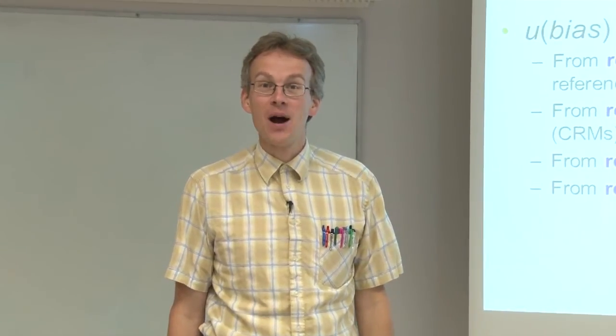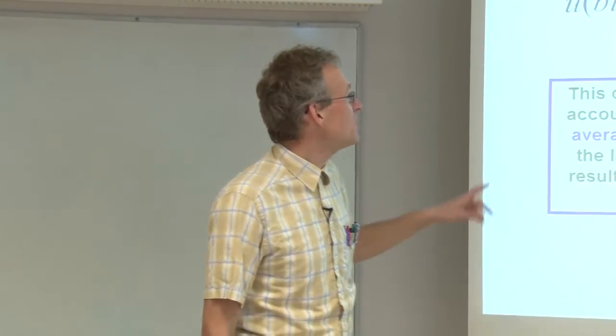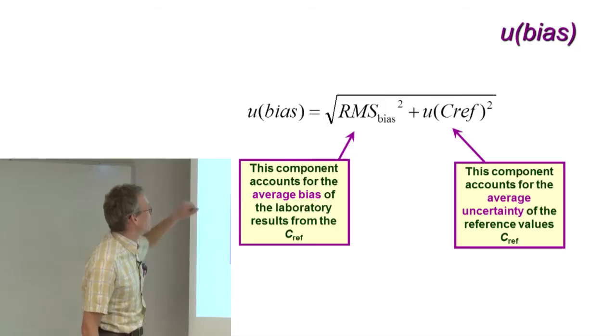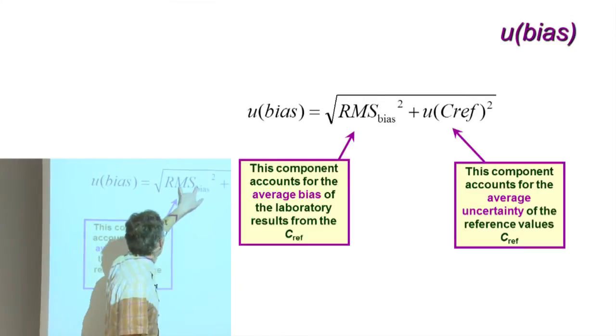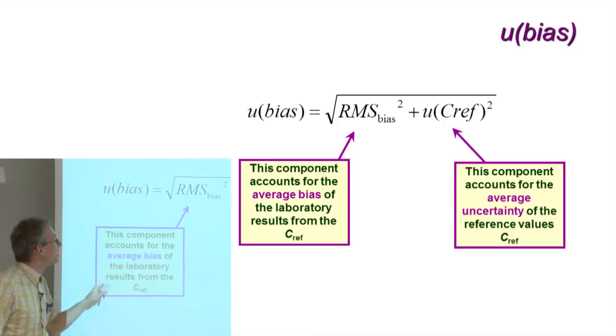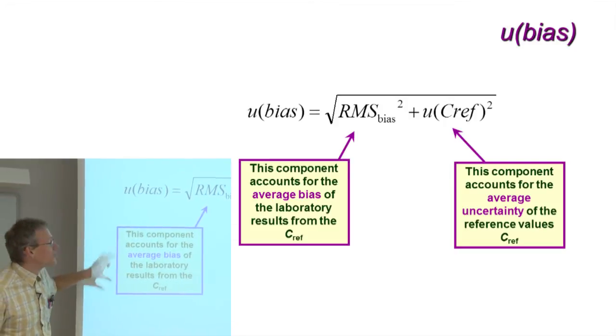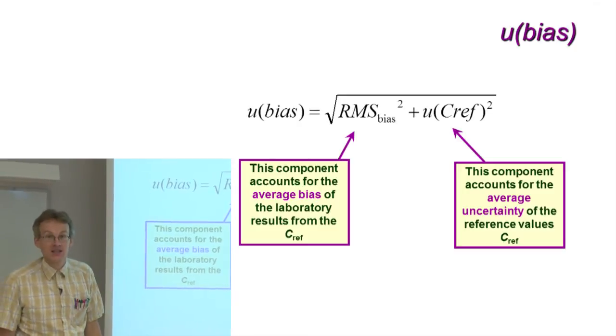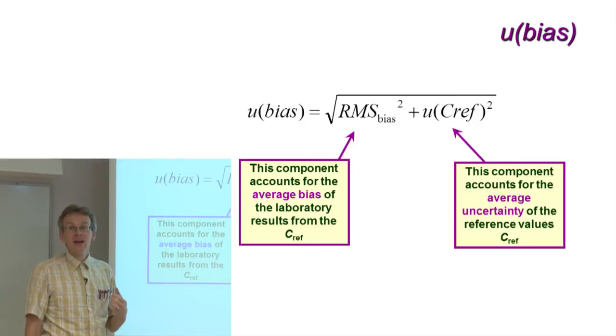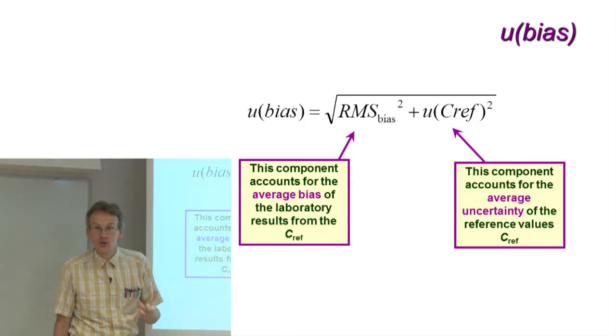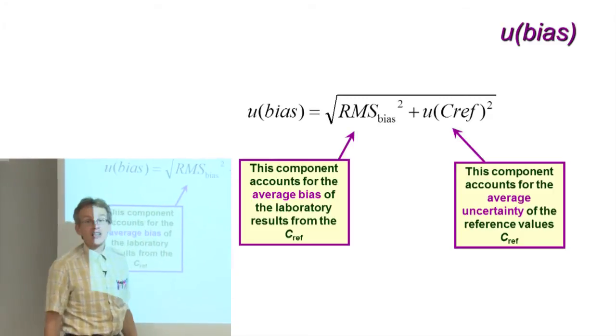Let us now see how we calculate this bias component. The main equation is presented here. U_bias is found as a combination of two uncertainty components. The RMS_bias accounts for the average bias in your laboratory — it is basically the averaged bias value, and I will show on the coming slides how it is calculated.